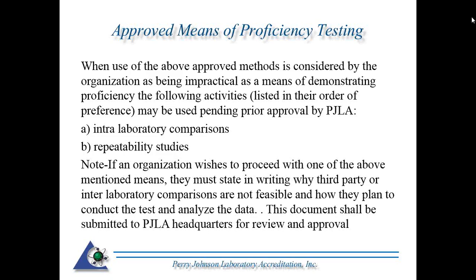So, for example, if you are doing temperature calibrations, calibrating RTDs, for example, there are plenty of third-party providers that do thermometers. Hence, the likelihood of a laboratory getting approved to do an intra-lab comparison would be at 0. So if we have identified a third-party source for doing proficiency tests, and the organization is able to utilize that source, we would require the organization to use the third party in lieu of either an Intra-Lab or a repeatability study. Again, if you feel it's not feasible, if there are no third-party providers, and it may not be practical to perform an Inter-Lab test.